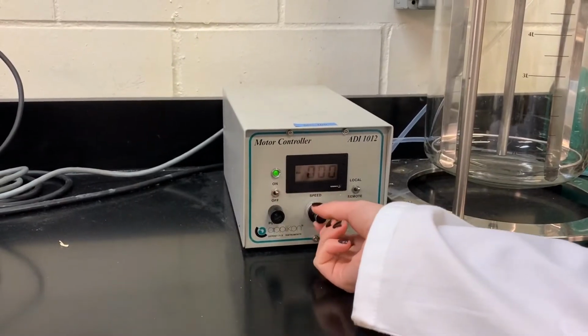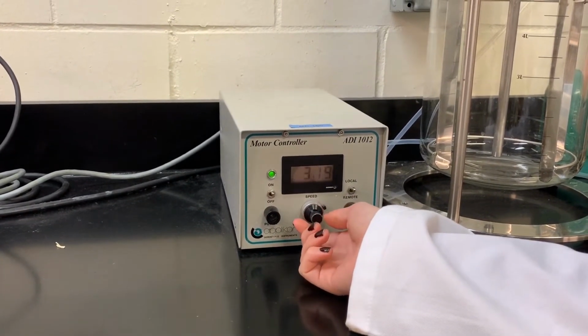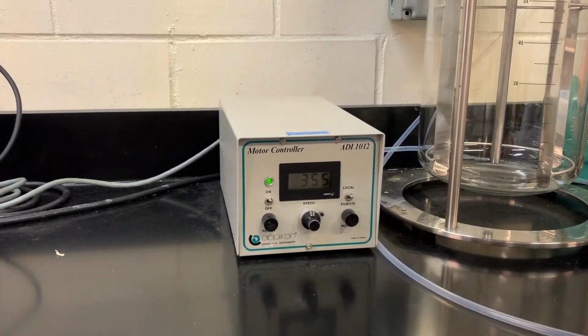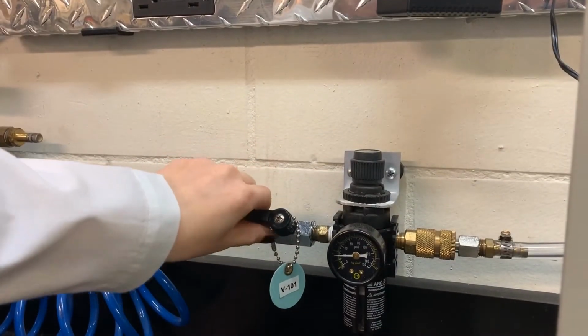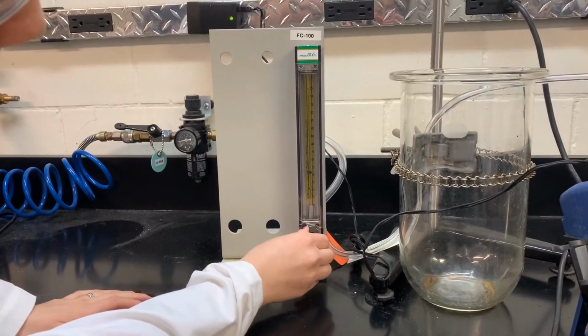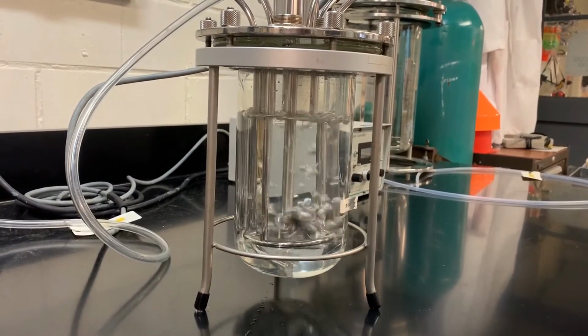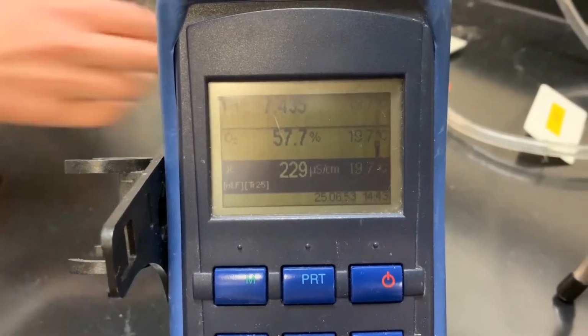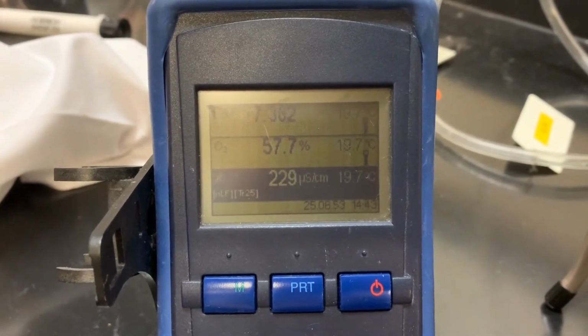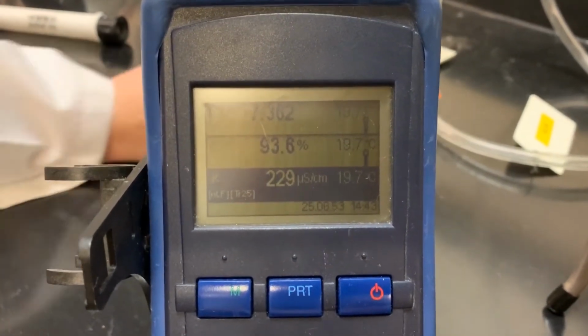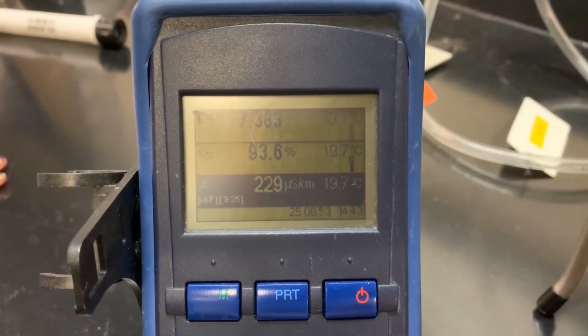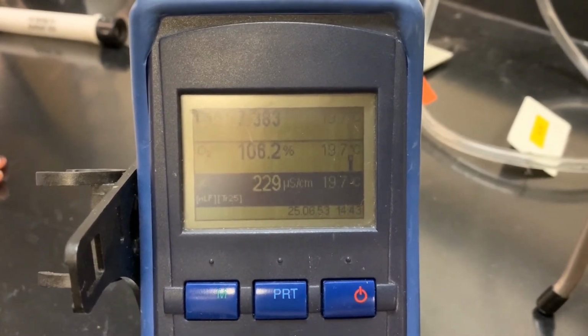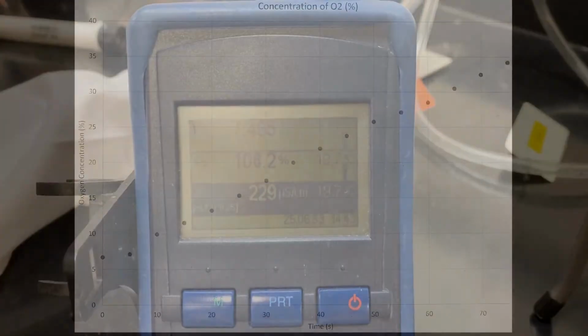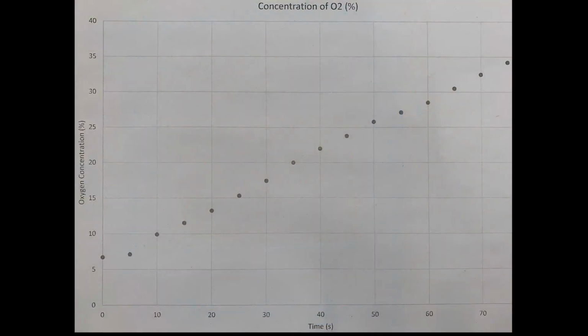To begin the first trial, set MC100 to the desired impeller speed. Open the air valve labeled V101 and set FC100 to the desired sparging rate. Upon setting the sparging rate, start the stopwatch to begin data collection. Record the oxygen percentage from the DO probe every 10 to 20 seconds. Continue recording the DO probe reading until sufficient data is collected to create a curve of oxygen concentration versus time. The graph of oxygen concentration versus time should stay fairly constant at first and then should increase linearly.